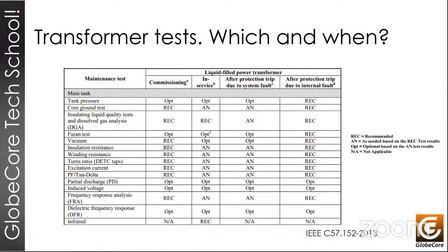So now the question comes, when and what exactly tests should we run? It's clear that the transformer has different stages in its lifetime. So the first stage would be commissioning. And this will allow or require us even to run a series of recommended tests. The IEEE C57.152/2013 test standard tells us that we can have 4 different scenarios. And in these 4 different scenarios, we'll have different recommendations for the tests that we're going to run.